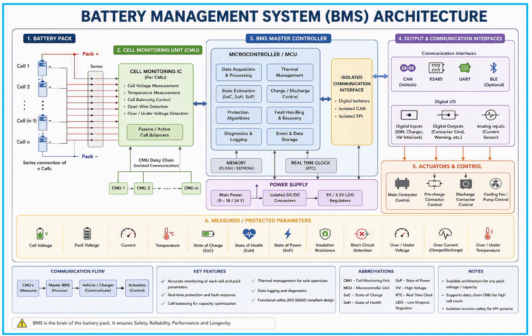Main functions include cell voltage measurement, temperature measurement, and cell balancing. In cell balancing, we have two types: passive cell balancing and active cell balancing. Then there's fault detection, which covers over voltage, under voltage, open wire conditions, sensor failures, communication errors, etc. All of this happens under the cell monitoring unit.